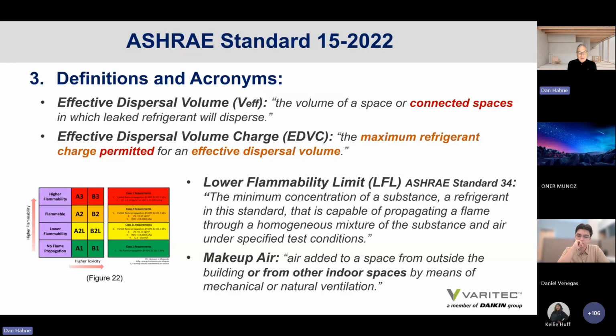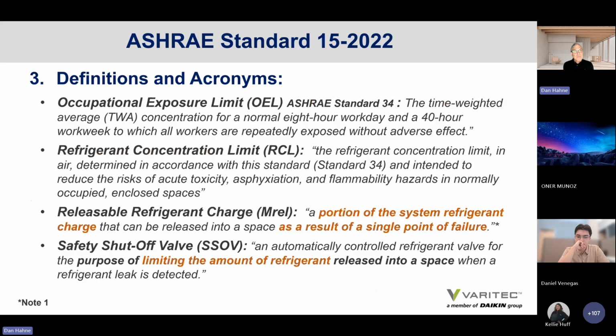What is makeup air? And this is an important term to understand. It is air added to a space from outside the building or from other indoor spaces by means of mechanical or natural ventilation. So makeup air in Standard 15 can be either outdoor air or even indoor air. It's not like ASHRAE Standard 62.1. Occupational exposure limits, we've already discussed. Refrigerant concentration limits is the refrigerant concentration limit determined in accordance with Standard 34 and intended to reduce the risk of acute toxicity, asphyxiation, and flammability.